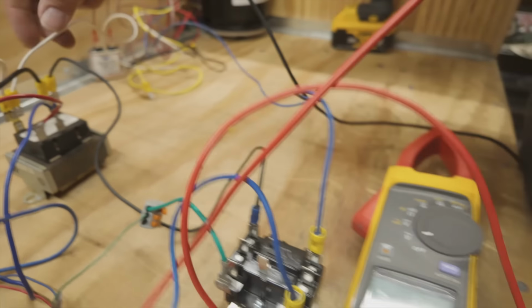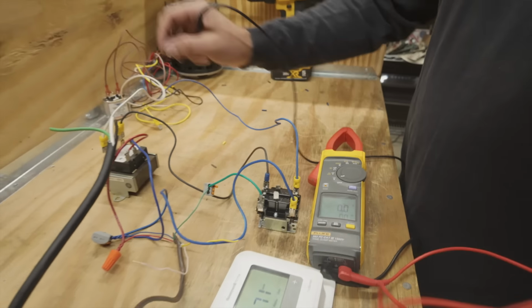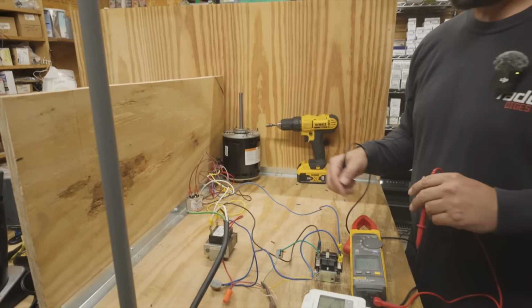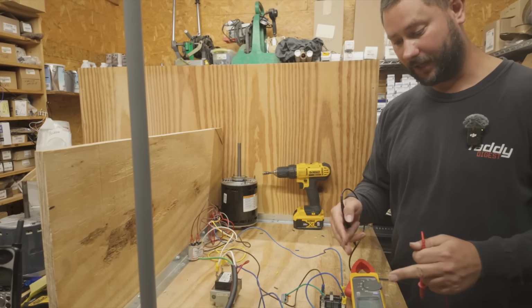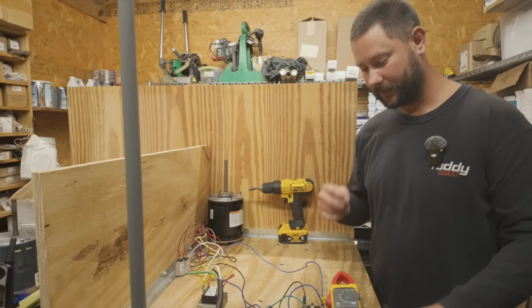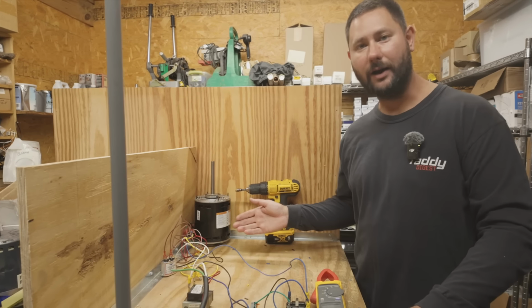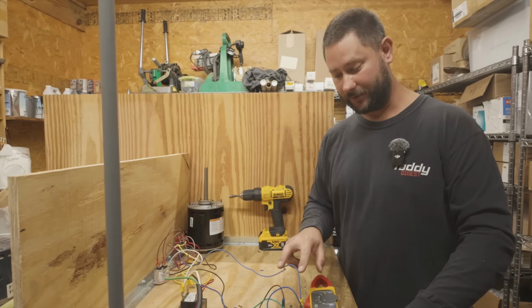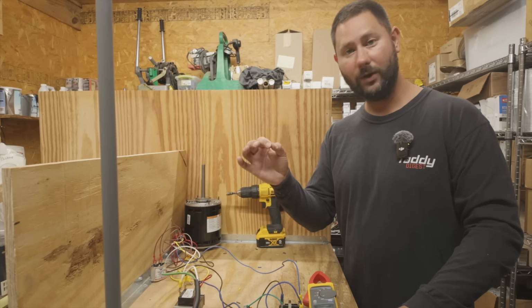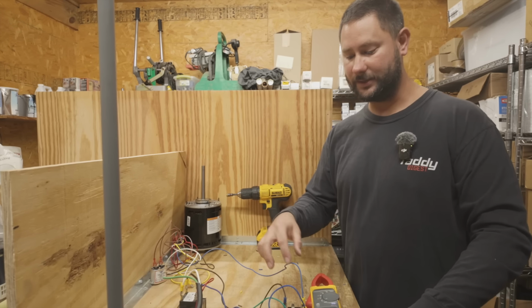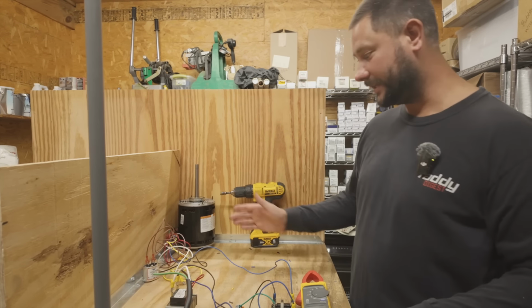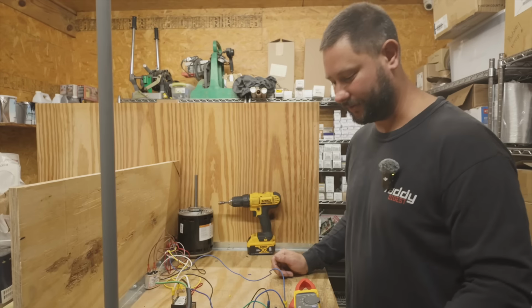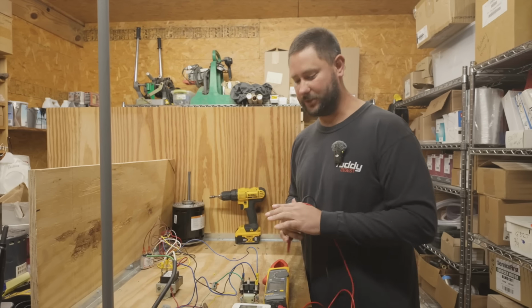We got 120 volts. One side of the line's going to our fan motor. The other side is going to a relay. And then on the other side of that contact, normally open contact, is a speed wire for our fan. So whenever the relay coil sends voltage, it energizes, closes the contacts, and sends that other side of the line to that fan motor. This is how to check a switching relay.